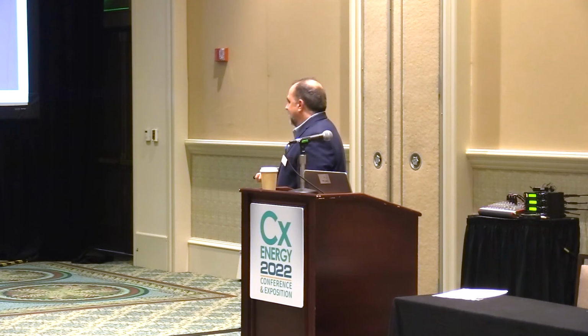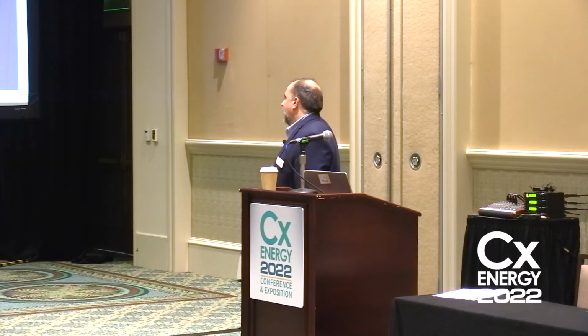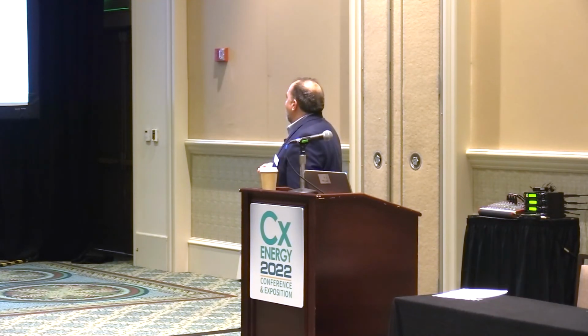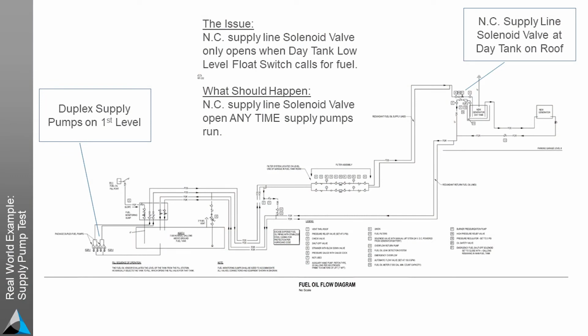I'm like, well, how am I going to blow up the system? Well, because the solenoid valve in the supply line up 8 stories in the generator enclosure is closed. I said, well, it's supposed to be. The sequence says that it's supposed to open whenever the supply pumps run. That's what happens. You run the supply pumps, they start, but they also open the normally closed solenoid valve in the line so that the fuel can actually flow. Well, there's a diagram, that valve was not opening. And so we got into this big discussion as to why that was the case, because it should be open. And they said the valve only opened when you pushed the run pump on the day tank that I was showing you in the slide earlier. And I said, that's not what's supposed to happen. It's supposed to open anytime the supply pumps run, so somebody doesn't do what I just did, 8 stories down, and run these pumps in hand.